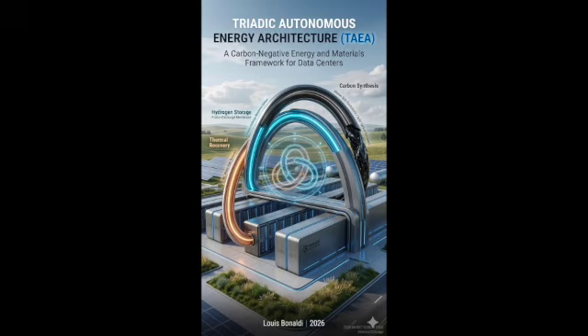When server loads are peaking and System 1 generates surplus power, the PEM system runs in forward mode. It uses electricity to split water and produce hydrogen gas. It banks the energy. And when the servers drop to idle and the heat vanishes? The system reverses. The hydrogen is fed into a fuel cell, which recombines it with oxygen. This not only generates electricity to keep the molten salt bath running, but the fuel cell itself generates high-grade heat as a byproduct. Oh, that's clever.